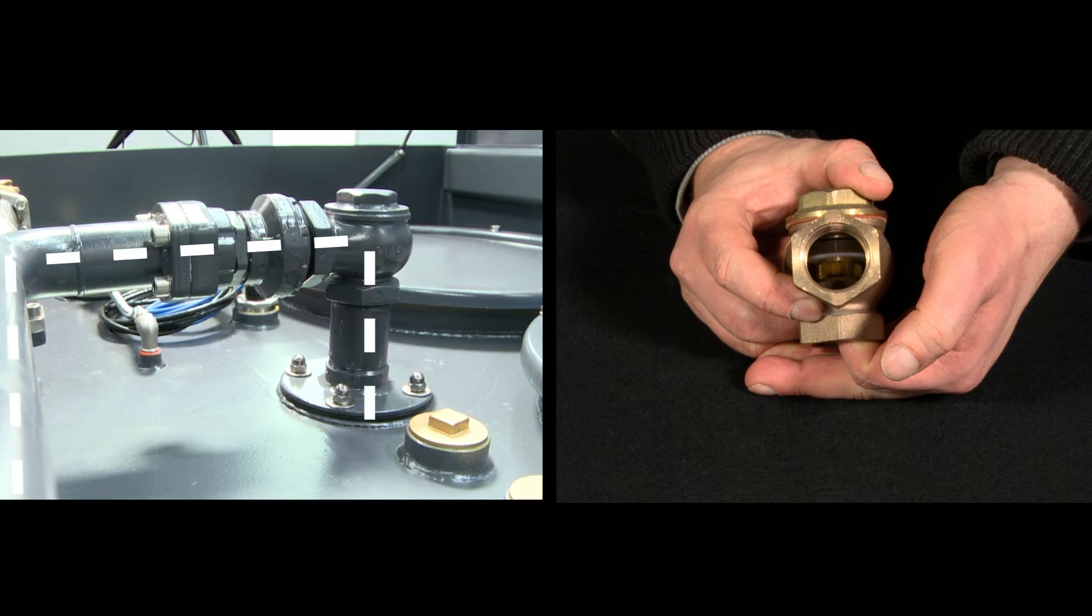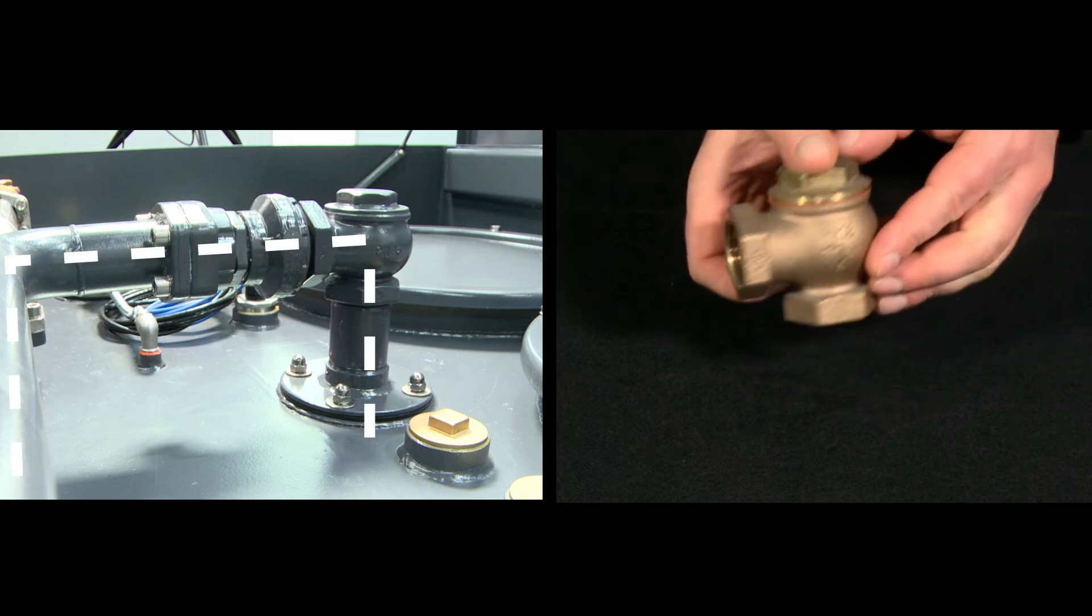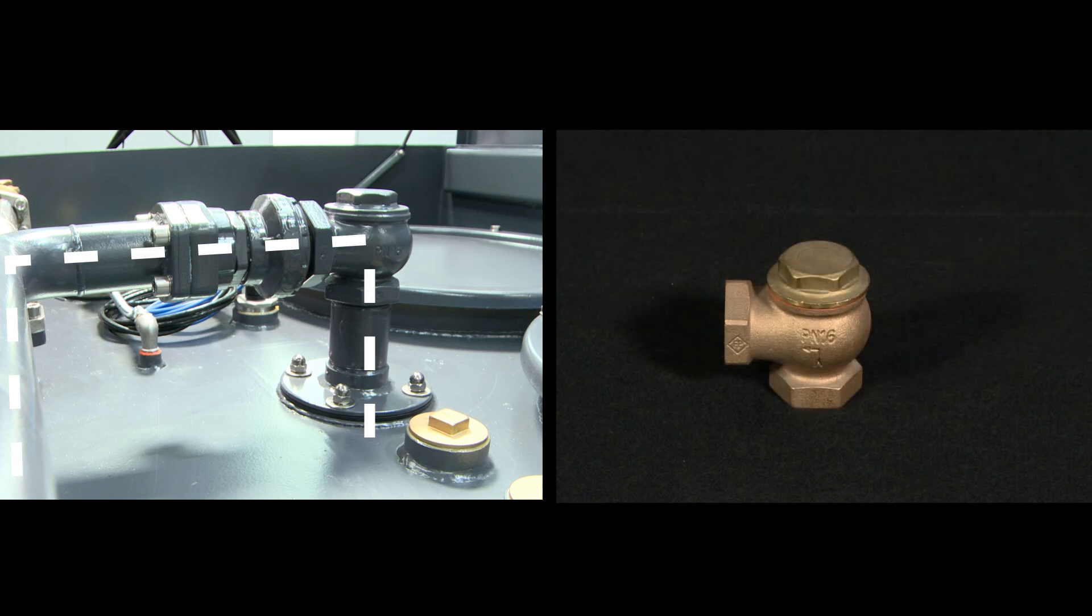At the end of refueling, the dispenser pump stops. The negative pressure drops and the valve cover closes. Thus, the suction line is blocked and a leakage of the tank is not possible.